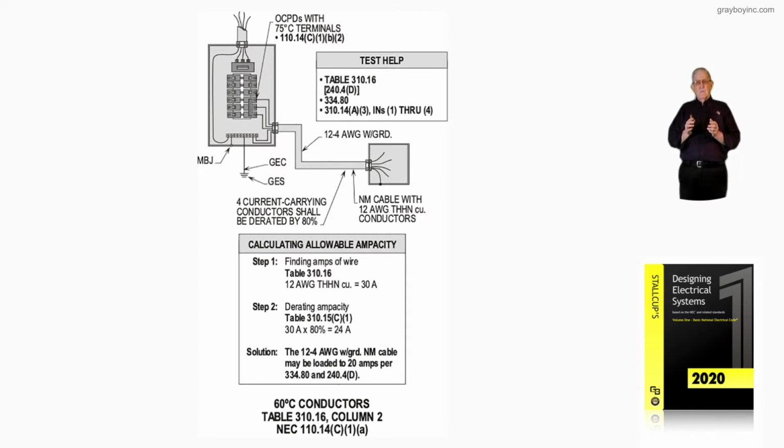Now the NEC loop says if you want to be a kind of wiser on this situation, with more knowledge to go by, review Table 310.16 and review the information at the very top of that table, because it gives you the temperature rating of those conductors have to be routed through an ambient temperature of 86 degrees Fahrenheit or less, point to point. And many inspectors, electricians, and designers will just apply a 10% rule. They won't route it through a higher temperature than 86 degrees, more than 10%.